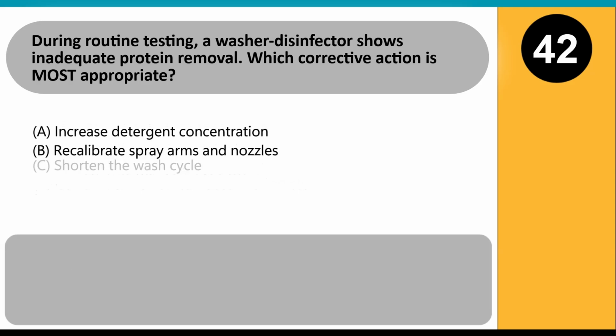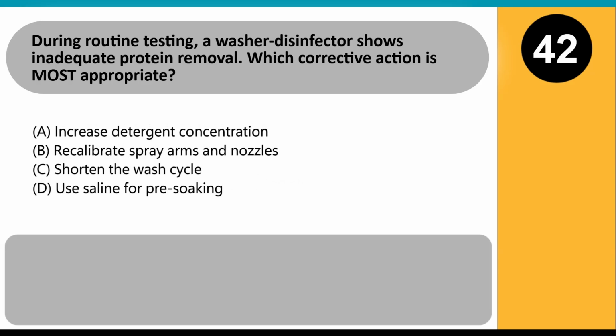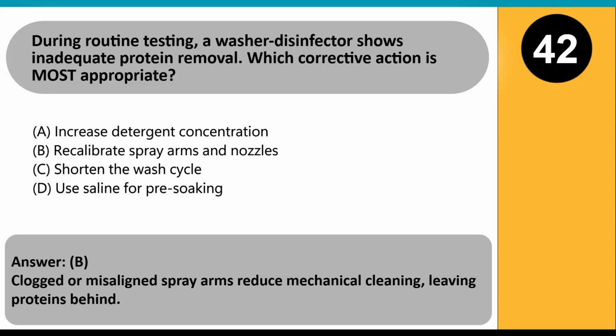During routine testing, a washer disinfector shows inadequate protein removal. Which corrective action is most appropriate? A. Increase detergent concentration. B. Recalibrate spray arms and nozzles. C. Shorten the wash cycle. D. Use saline for pre-soaking. Answer: B. Clogged or misaligned spray arms reduce mechanical cleaning, leaving proteins behind.